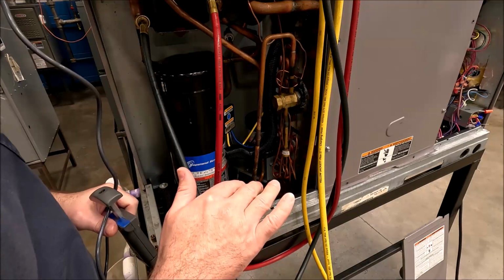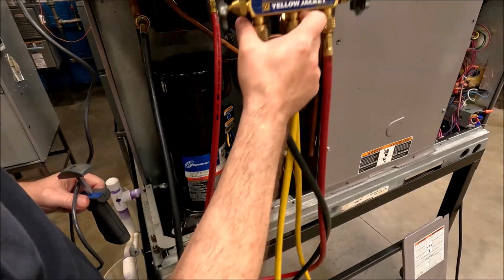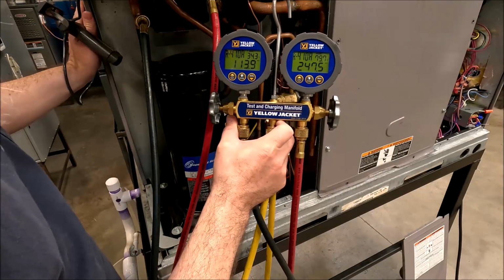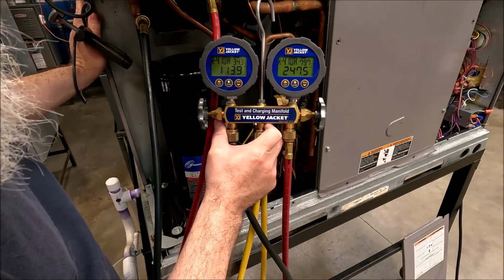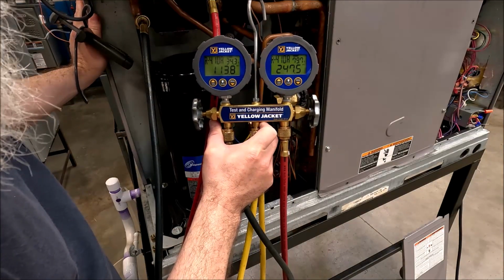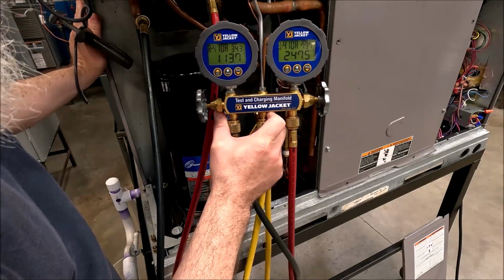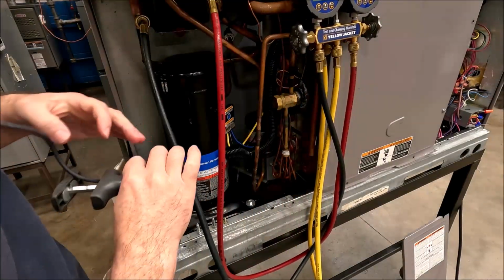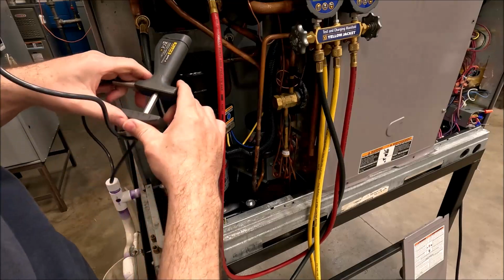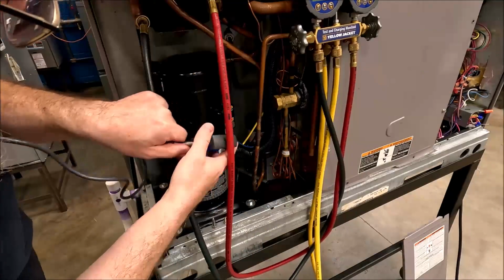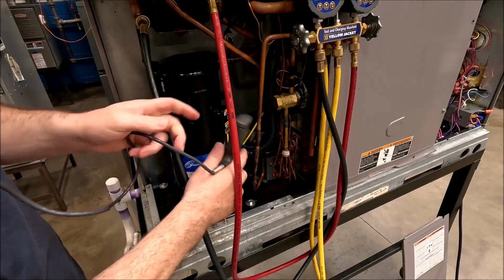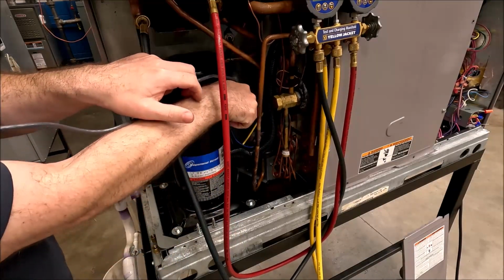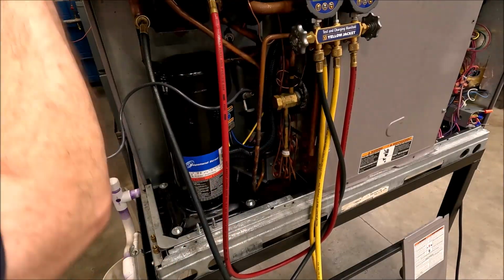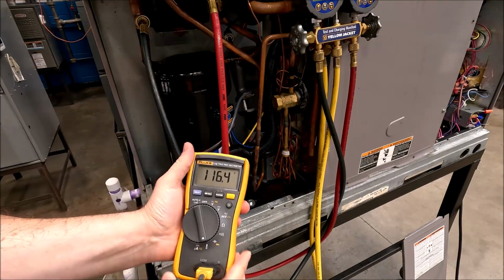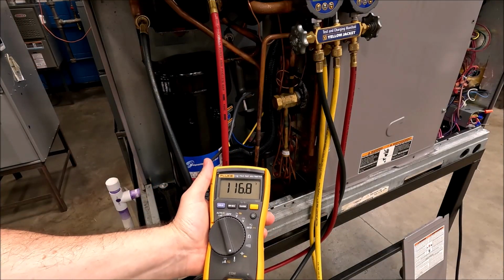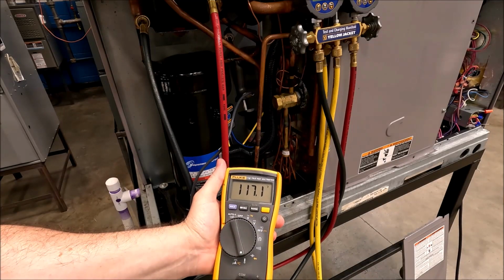is the saturation point. So right now we currently have 247.5 psi. That gives me a saturation point of 79, almost 80 degrees. All right, if I were to clamp that line, you're not gonna get, and it's a little harder on this one, as with a lot of package units, right? So let me get up in here. If I were to clamp that line, you can easily see that we're going up almost to 120 degrees.